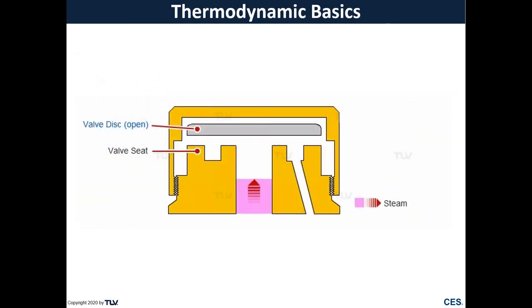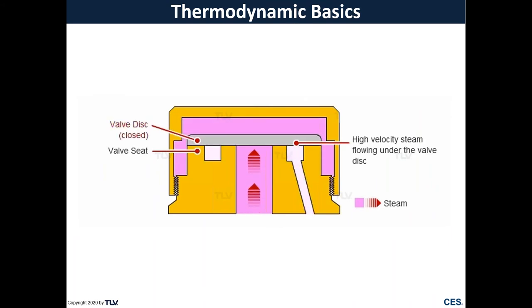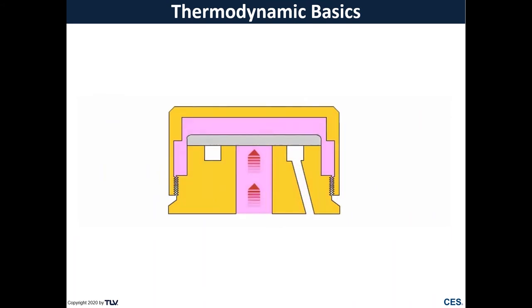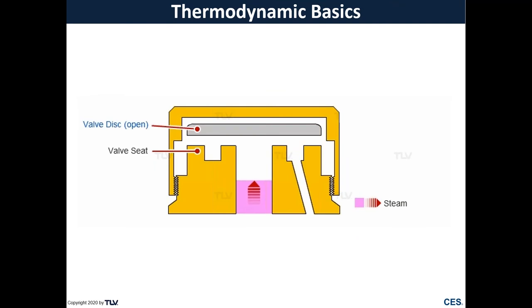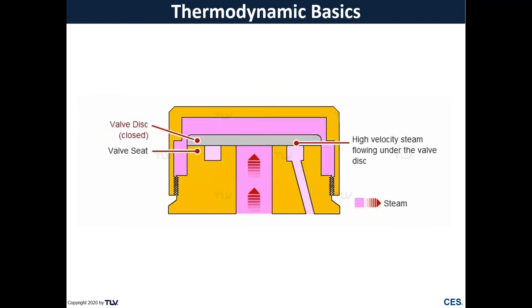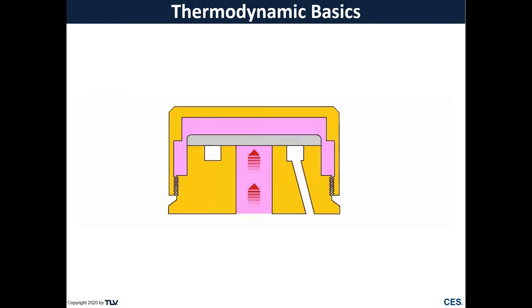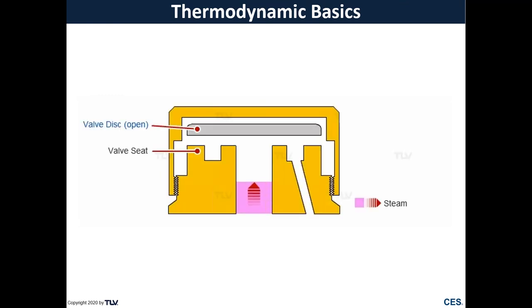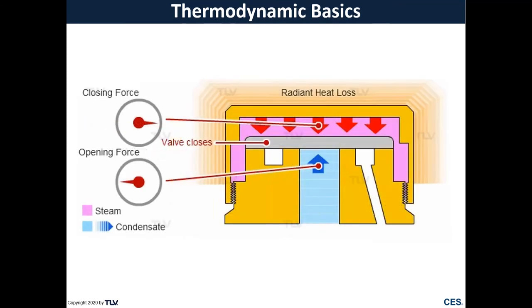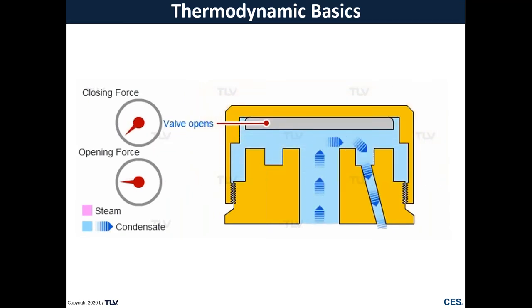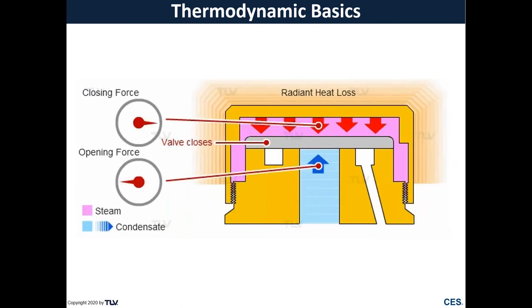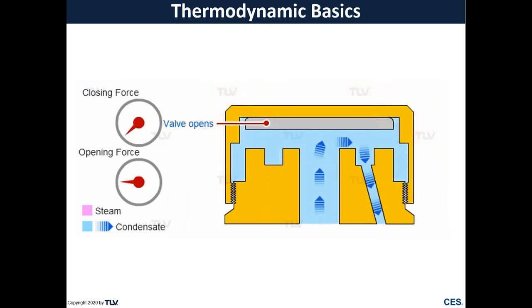Now, how does that work in a disc trap? Well, as steam is pushing condensate through this trap, condensate won't really have that high of a velocity. And then as soon as steam reaches the bottom side of that disc, that steam is going to wick across the bottom side of the disc, creating a localized low pressure, pulling the disc down into the seating surface. Once that disc is shut, there's actually a small pocket of steam that gets trapped on the top side of the disc. Now, with radiant heat loss, that pocket of steam will slowly condense, losing the closing force, because that closing force is pushing down on the disc, and our inlet pressure and our back pressure are pushing up on the disc. Once that force dissipates, the disc will then open again.